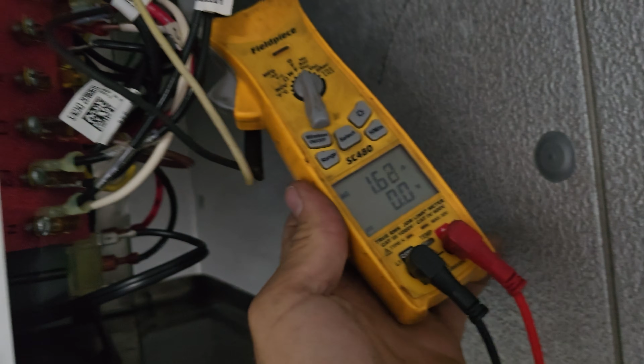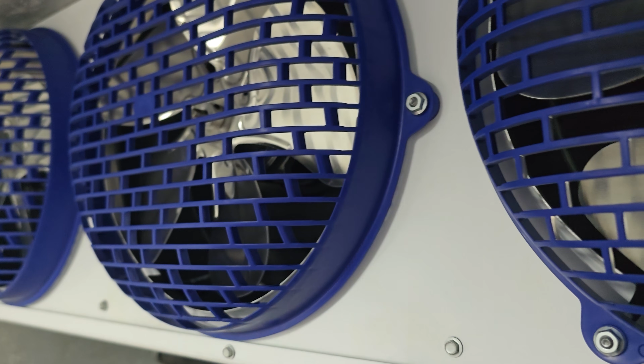So the unit's satisfied, and I put it into a defrost. You always want to test defrost, make sure that all the heaters are working. So I'm up here just testing the heaters, making sure they're good, but defrost is working, pump down's working. We're looking really good. So while it's in defrost, we're just kind of monitoring the settings. We have it set to terminate defrost at 60 degrees or 20 minutes.